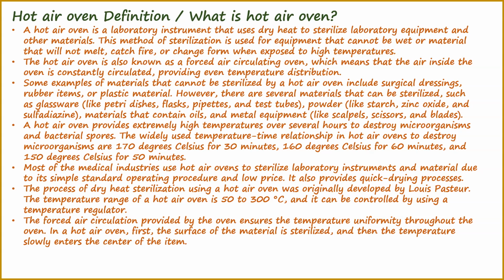This method of sterilization is used for equipment that cannot be wet or material that will not melt, catch fire, or change form when exposed to high temperatures. The hot air oven is also known as a forced air circulating oven, which means that the air inside the oven is constantly circulated, providing even temperature distribution.